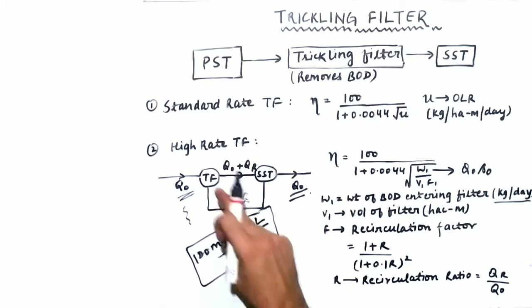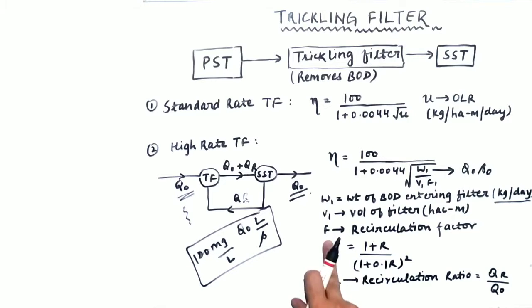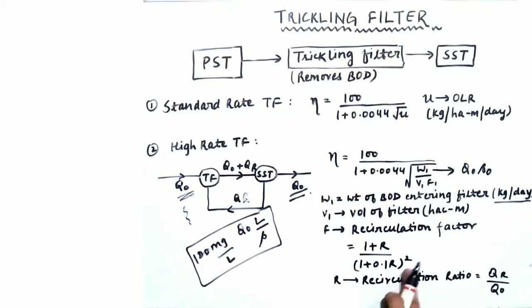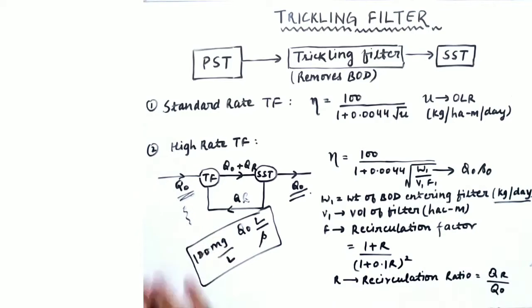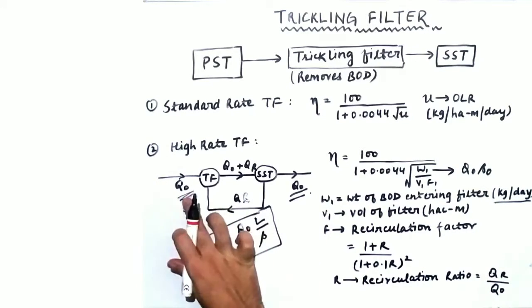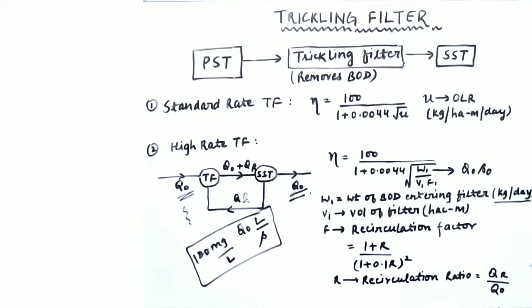V1 is the volume of the trickling filter. F is called the recirculation factor, calculated as F = (1 + R) / (1 + 0.1R)², where R is the recirculation ratio. The recirculation ratio R is the ratio of the recirculated discharge QR to the incoming discharge Q0.